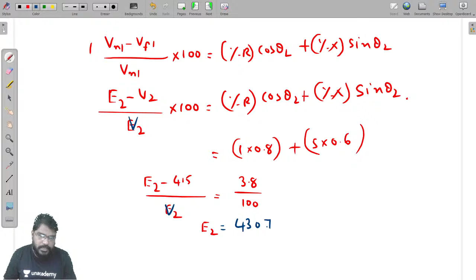V2 phase value is equal to 430 divided by root 3. But we required turns ratio. Turns ratio is equal to 6000 divided by V1 phase divided by V2 phase. So V1 phase is 6000, V2 phase is 430 divided by root 3. Now simplify this, you will get nearly 24.12, so it is nearly equal to 24. Like this we have to calculate.